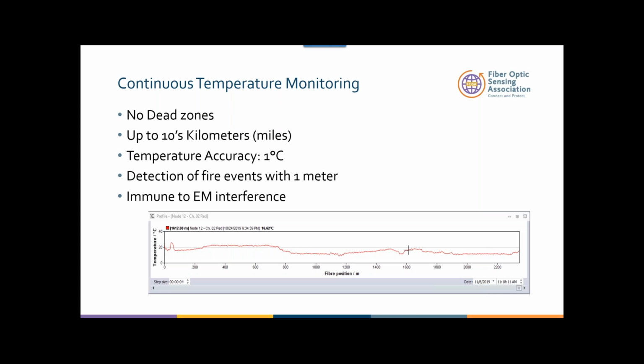structure or equipment. So in this case, you can reach an accuracy of 1 degree Celsius. You can know within a meter where it is, but most importantly, you also can see the trend of the events. And last but not least, it's immune to EMF, electromagnetic interference, so EMI. It's very, very important to point that out, because this sensing cable can be installed in many other areas, as we're going to talk about within the webinar.